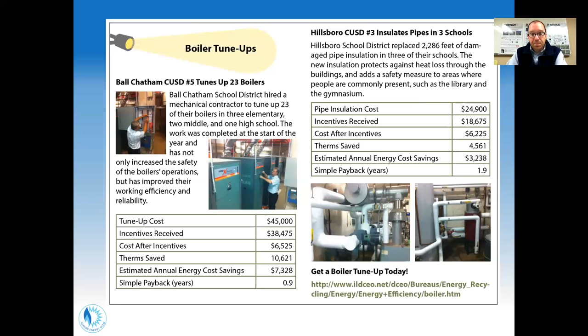Related to the boiler program, there are also pipe insulation programs. The second example involved replacing failed pipe insulation where pipes were completely exposed, raising a life safety concern. Sometimes people are able to apply other funds, like life safety funds, to help pay for remaining costs. The pipe insulation project cost $24,900, received almost $19,000 in incentives, and is saving $3,000 a year—about a 2-year simple payback. These are excellent examples of what to do to save gas energy in buildings.